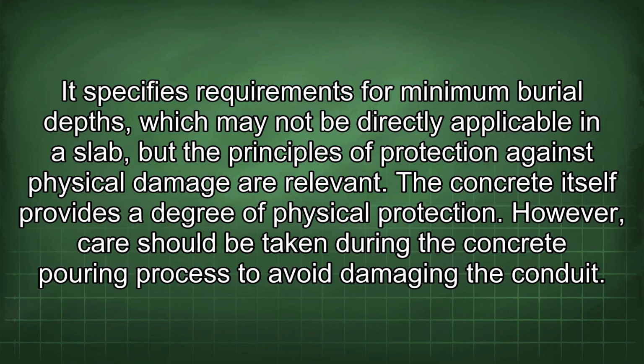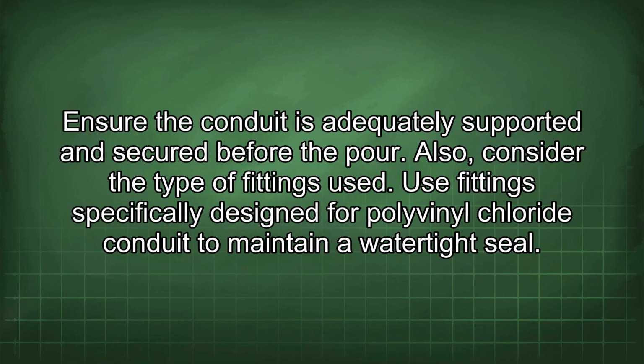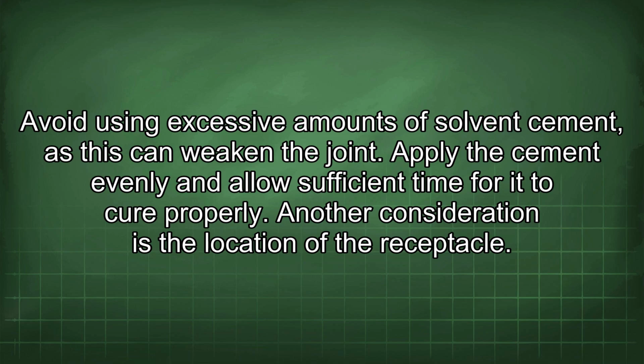The concrete itself provides a degree of physical protection. However, care should be taken during the concrete pouring process to avoid damaging the conduit. Ensure the conduit is adequately supported and secured before the pour. Also, consider the type of fittings used. Use fittings specifically designed for polyvinyl chloride conduit to maintain a watertight seal. Avoid using excessive amounts of solvent cement, as this can weaken the joint. Apply the cement evenly and allow sufficient time for it to cure properly.